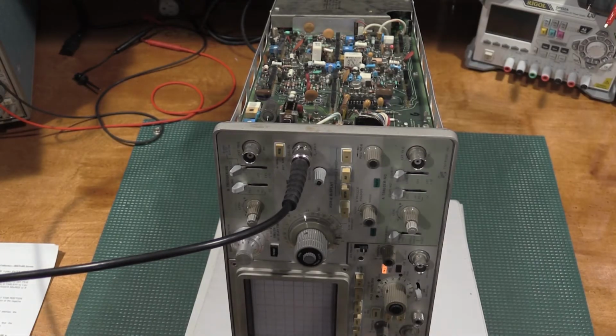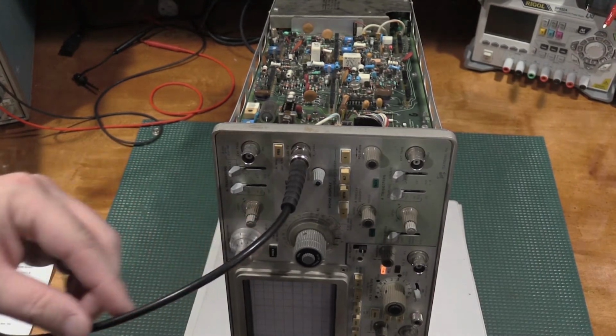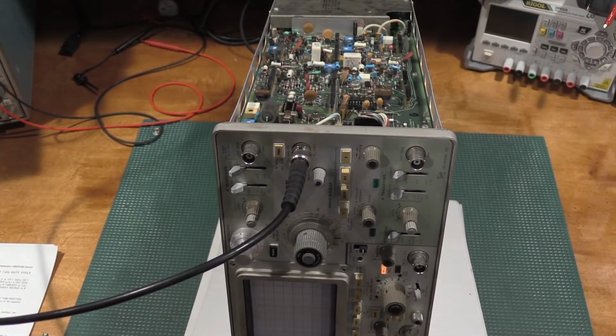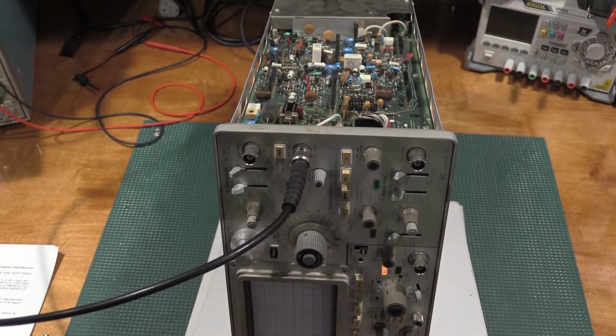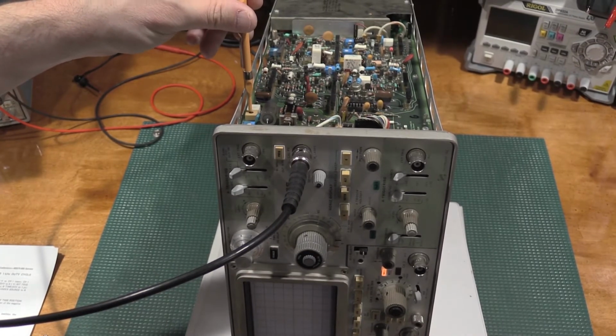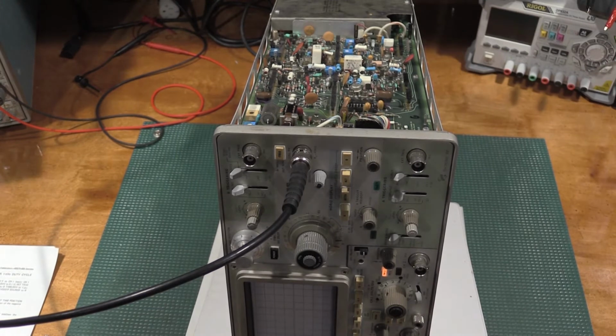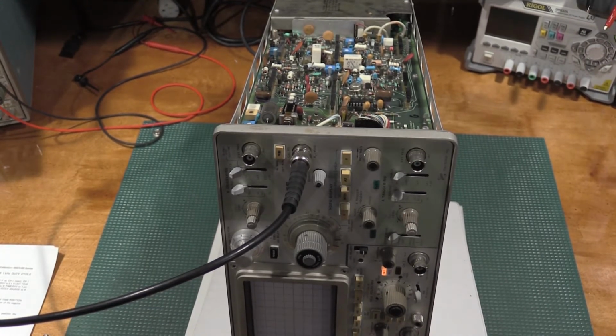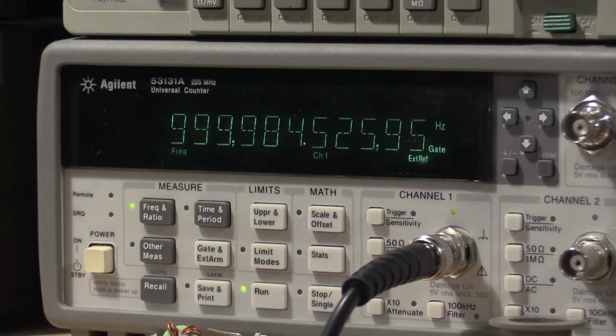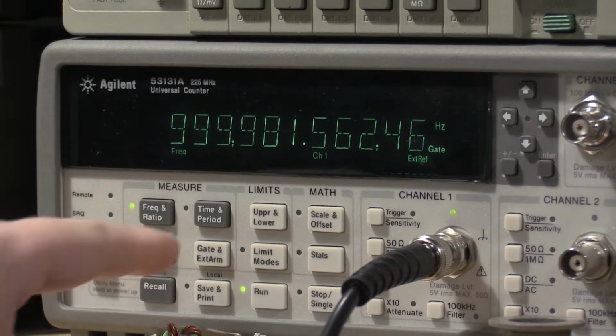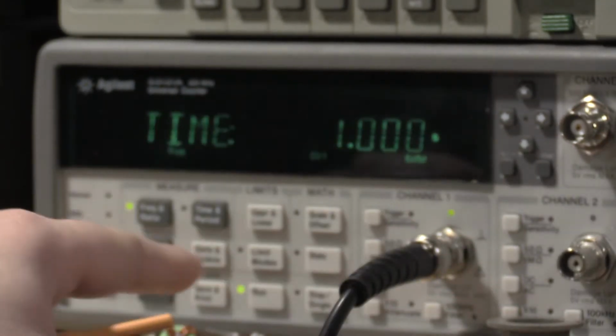Okay, so the calibration routine wants us to do a bunch of stuff with a scope and a few other things to set the frequency of the calibrator. I have a frequency counter with enough digits, and it's backed up by a rubidium standard, so we're just going to calibrate directly to the frequency counter. It is off. This is the potentiometer I'm going to be adjusting, and I will move you guys up to the frequency counter. Okay, so we want to adjust this for as close to 1 kilohertz as possible, and I need to speed this up so I can actually see it adjust, because I just really shot it into outer space.